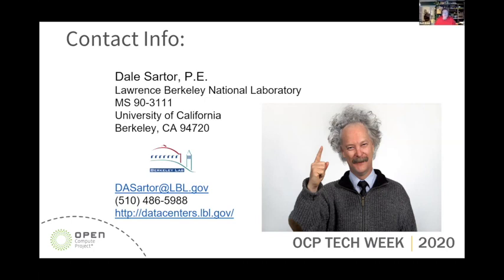Yeah, Dale, I just want to apply a little correction on where you refer to me as the source on the slide with all the temperatures. The temperatures and temperature ranges that you showed are not industry-wide references. They're case-specific references in a paper that illustrates how you can deal with specific requirements. So the tolerances are not determined by the technologies, but by the IT specification that the technology at that point in time is cooling.